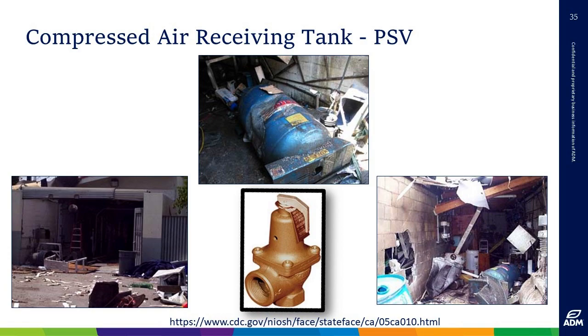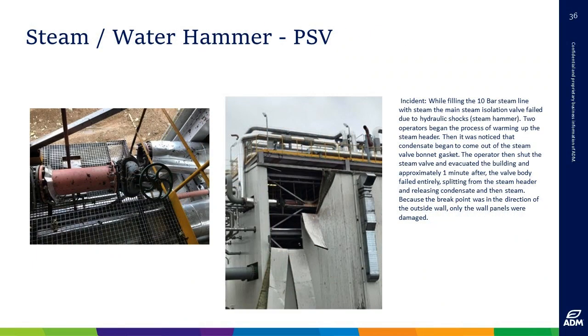This was at a facility we have in Europe, commissioning a steam system, hot commissioning, running steam in it. We just put all the piping in. Water hammer, you can see on the left, it blew the pipe out and just ruptured the panels on the walls. So maybe you don't have high pressure steam, but it doesn't take much.